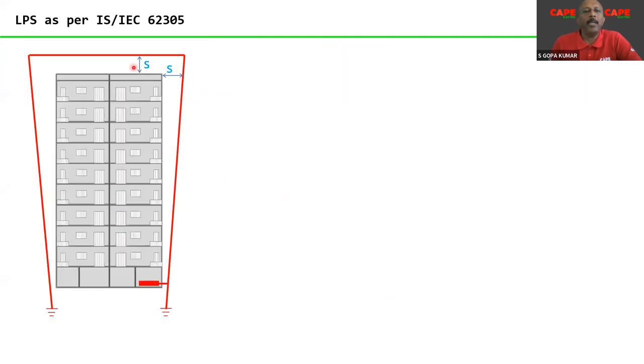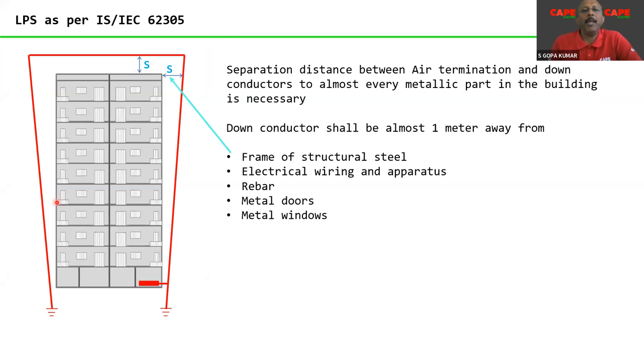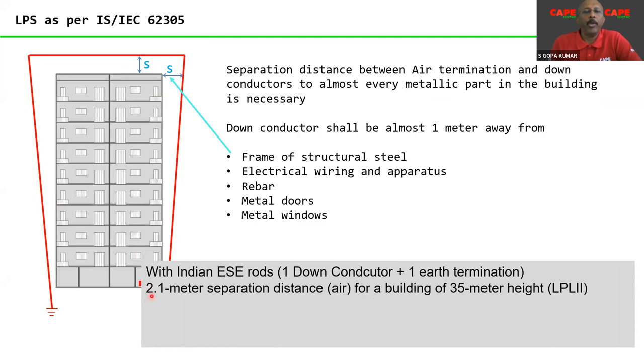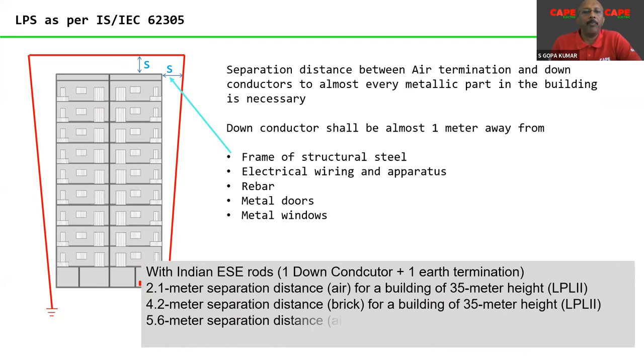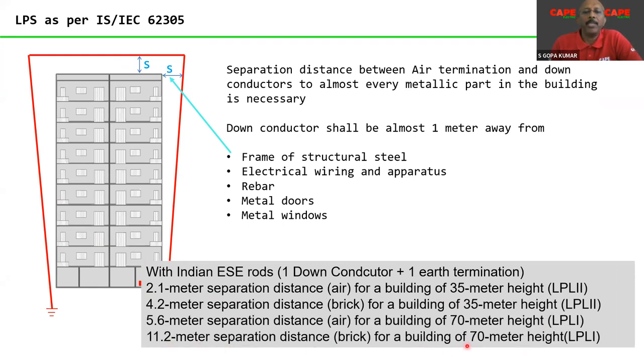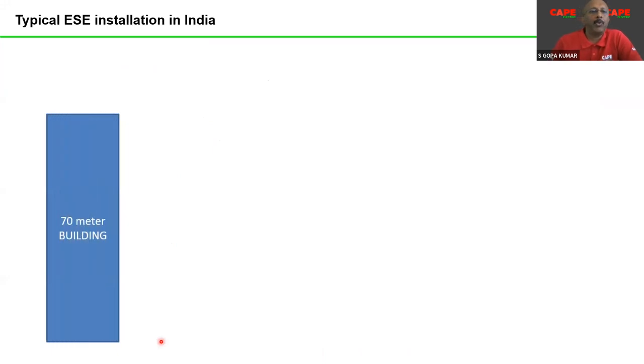What does it mean? It means the ESE rod and the down conductor have to maintain the separation distance in the typical Indian way, one down conductor. In that case, the separation distance required is 2.1 meter for a 35 meter building with level 2, almost 11.2 meters for a 70 meter height building with LPL 1, where we consider the separation material is brick. So much distance away from the building. That means if you look at the actual scenario, for a 70 meter building, the air termination and the down conductor have to be physically away from the building. How much physically away? 11.2 meters physically away from the building.